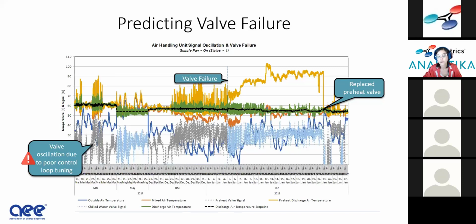That's an indication of a passing valve, I should say. So we can see a huge preheat discharge. The savings on this are huge, and here's the reason. We're heating 30 degrees, and then we're cooling 30 degrees to get back down to temperature.